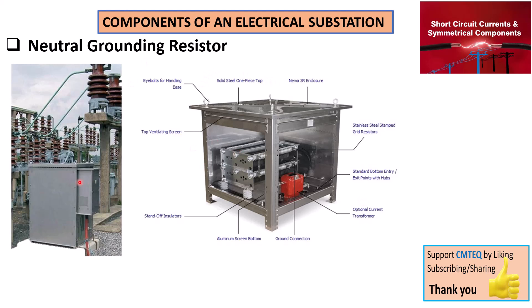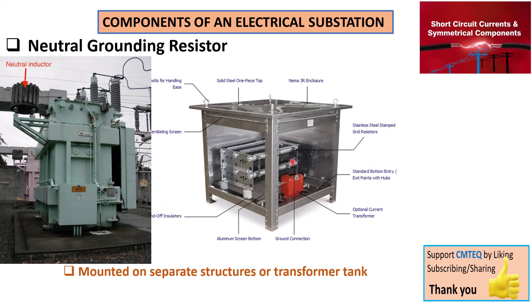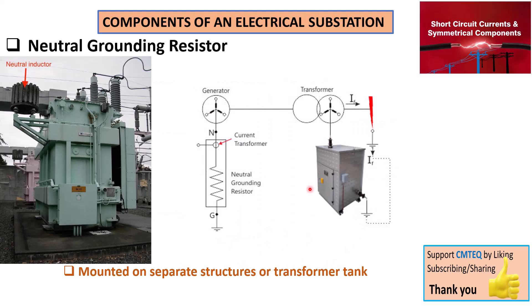As this device is mounted on top of a transformer or somewhere near a transformer, its main purpose is to provide the shortest path for the current to flow to the ground. Electrical current is always trying to return to the source where it comes from by choosing the path with the least resistance. So by providing a neutral grounding resistor through the transformer neutral point, we are basically providing that path for the current to flow.